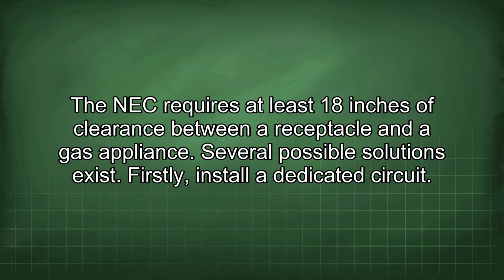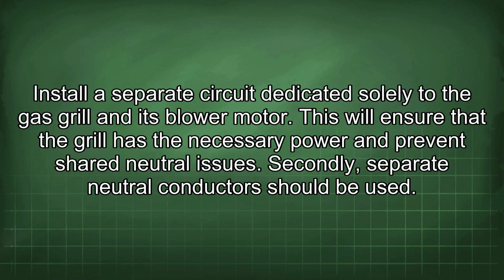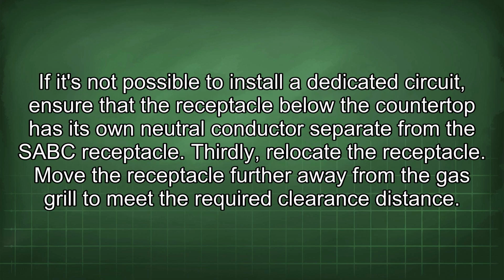Several possible solutions exist. Firstly, install a dedicated circuit. Install a separate circuit dedicated solely to the gas grill and its blower motor. This will ensure that the grill has the necessary power and prevent shared neutral issues. Secondly, separate neutral conductors should be used. If it's not possible to install a dedicated circuit, ensure that the receptacle below the countertop has its own neutral conductor separate from the SABC receptacle. Thirdly, relocate the receptacle. Move the receptacle further away from the gas grill to meet the required clearance distance.